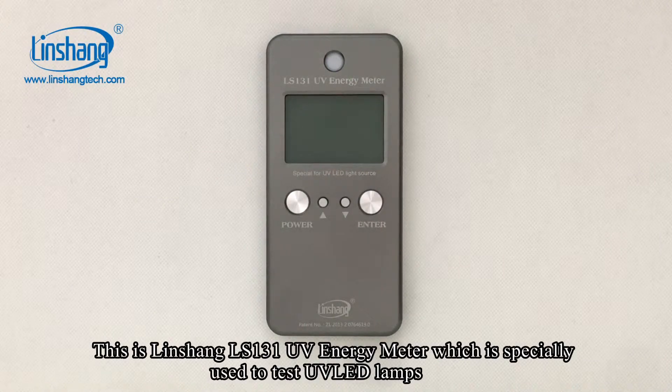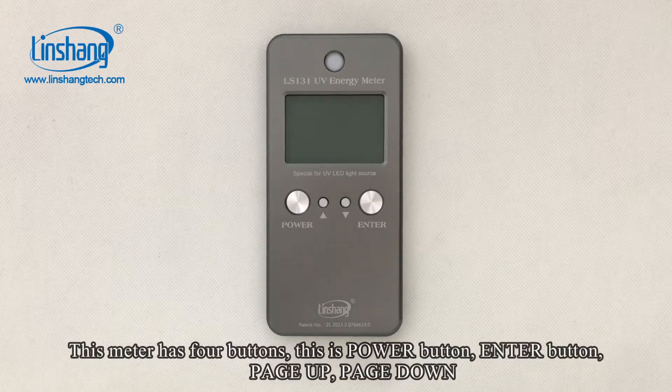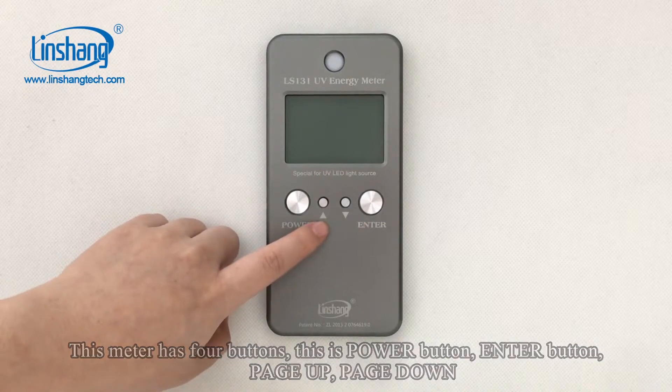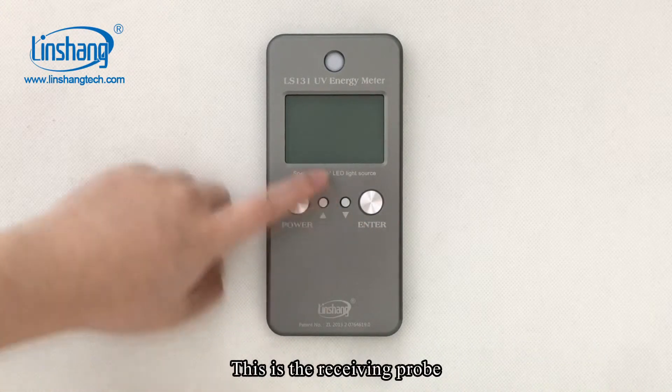This is the Linshang LS131 UV energy meter, which is especially used to test UV LED lamps. This meter has four buttons: the Power button, Enter button, Page Up, and Page Down. This is the receiving probe.